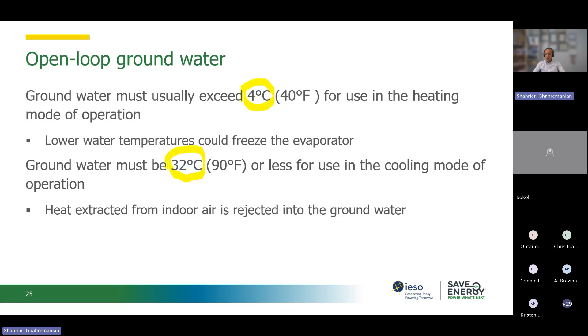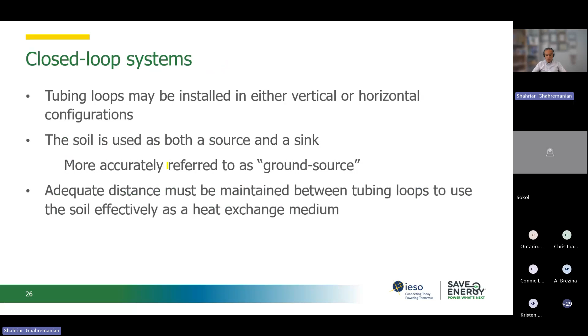For the ground source heat pump, we can also have two types. One uses the ground temperature, which is the soil. Across the GTA, on the projects I've worked on, the temperature is usually between 8 and 10 degrees Celsius all year around under the ground. And if we have a well or water source under the ground, maybe we can connect our closed loop to it and exchange heat with that water. So the ground and water source heat pumps can both be used for our purposes.